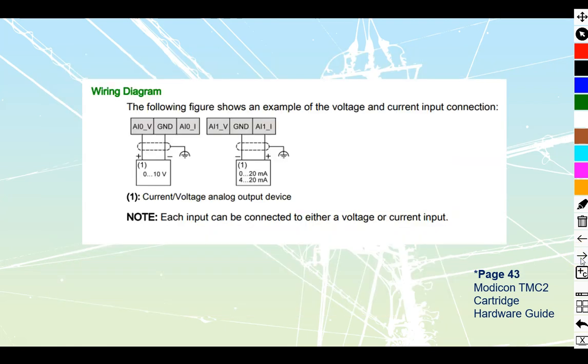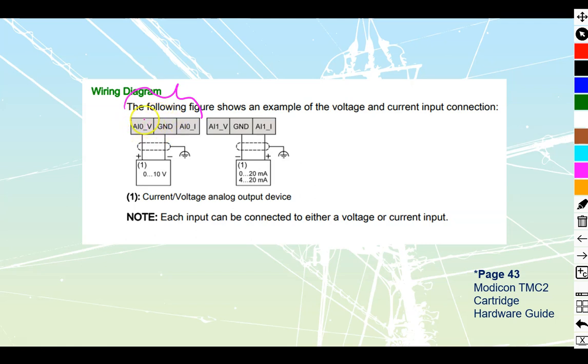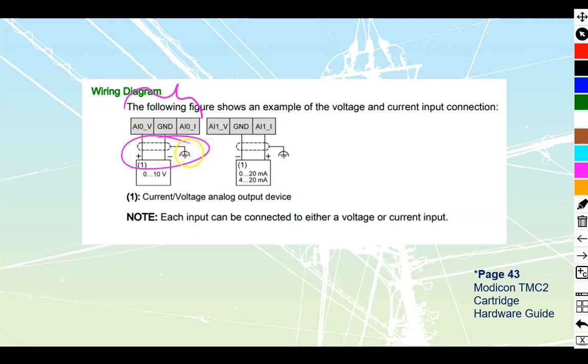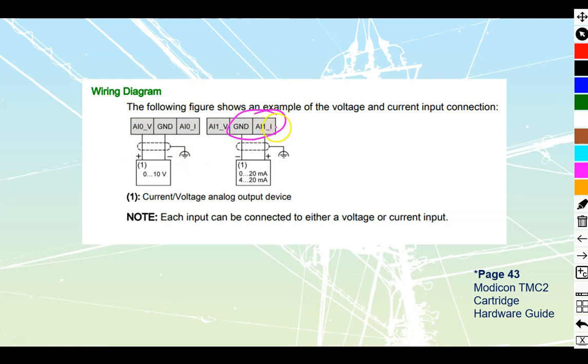Let's look at the actual wiring. From the manufacturer's diagrams, we have a set of three terminals placed together. The terminals both use the same ground. If I'm using voltage, this is AI zero V—that's a voltage input. I would take my positive voltage into there. They show the shield is going to have to be grounded down, or alternatively I can take in current using the ground and analog input which ends with an I.